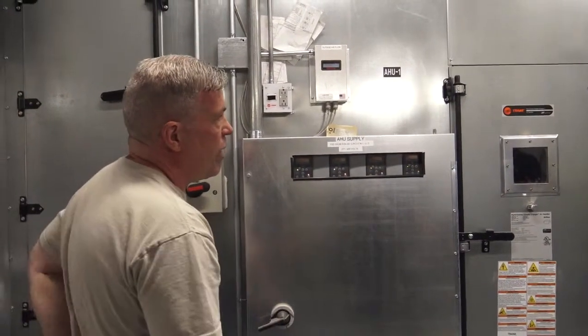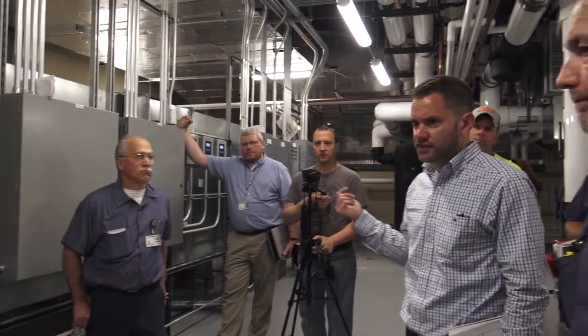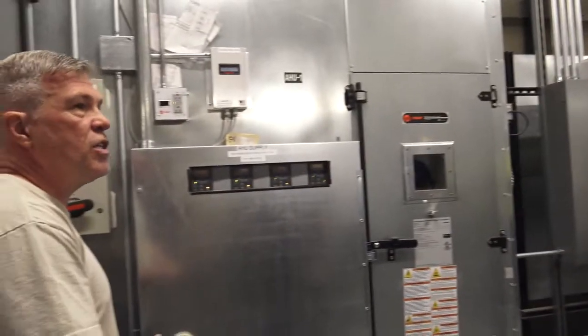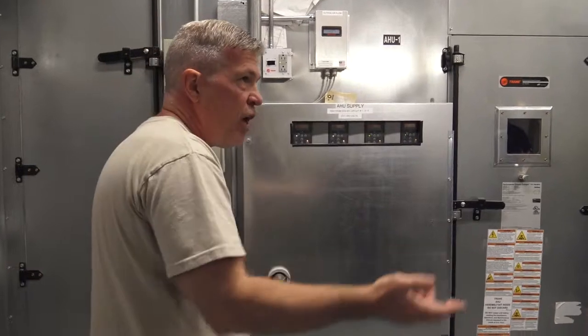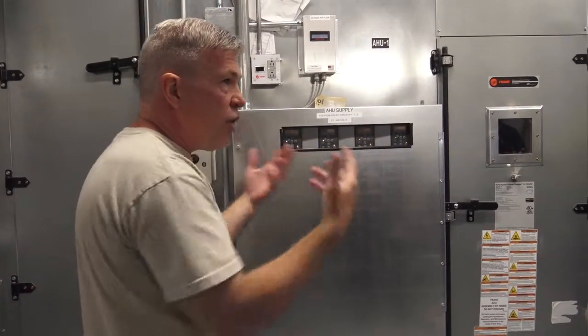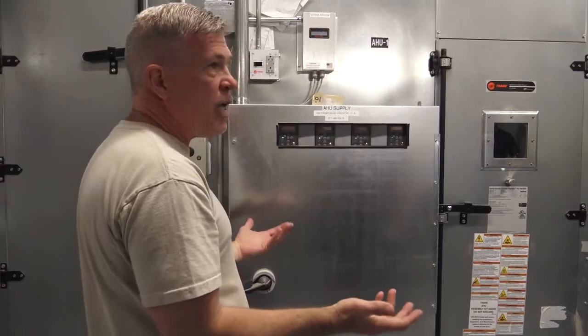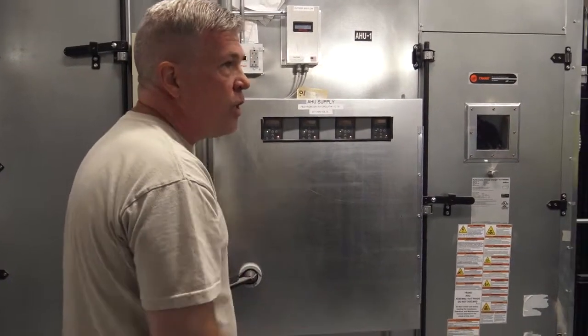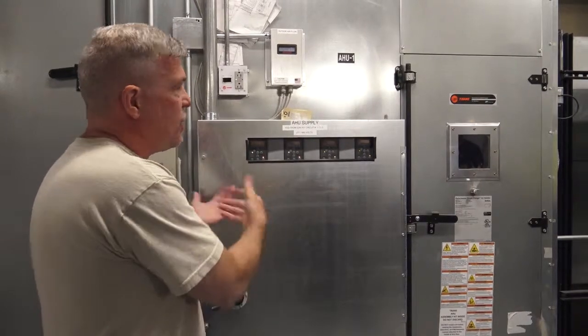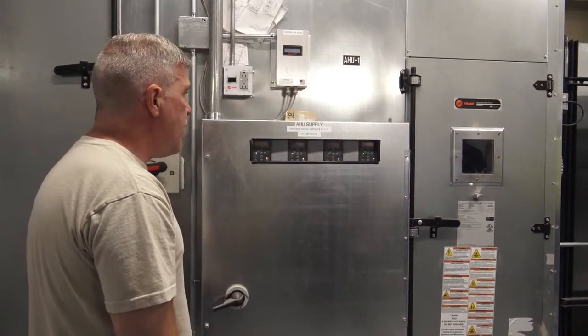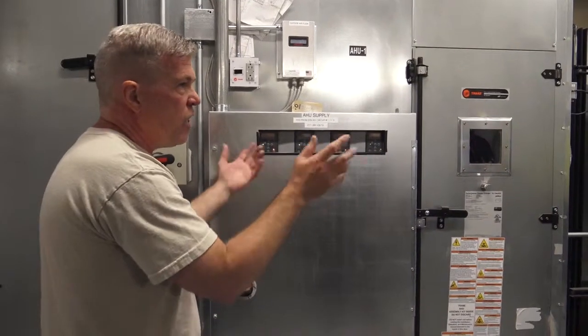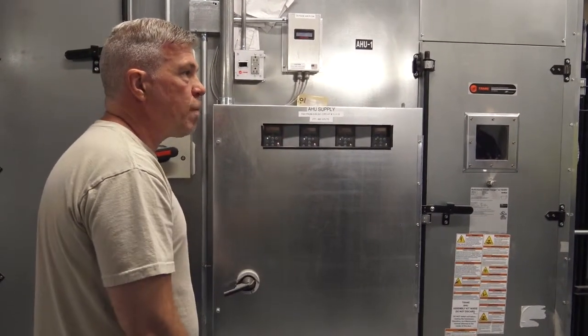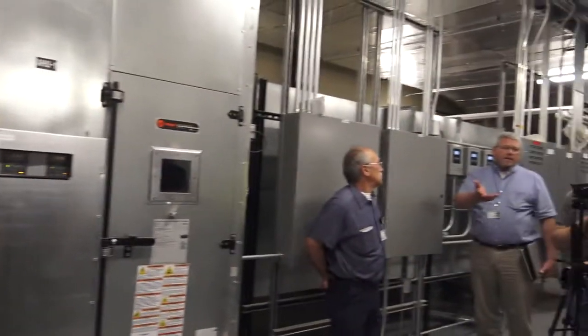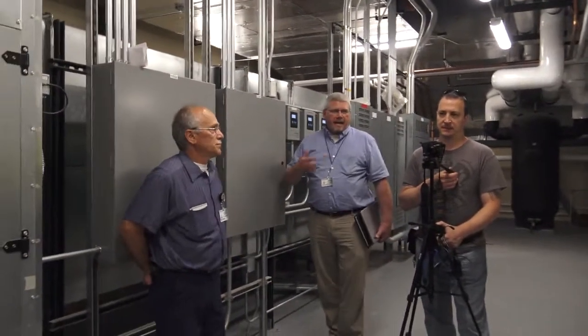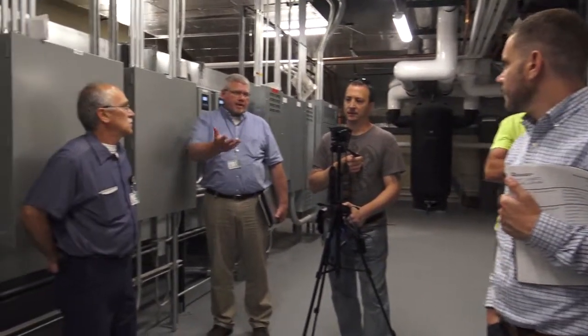So, thing to remember. Is there an alarm on your building automation system? Does John get a text message if that goes down? On the automation system, they would see it say supply fan number 3 failure. It can email out and all that if that's what they want set up. It's there to do it if they want to. We haven't done too much of that because usually someone is monitoring it somewhere, but we can do all the alarming and text messaging if necessary. We've never set it up because the power plant monitors it 24/7, and the hospital guys have access to it 24/7 too. Okay.